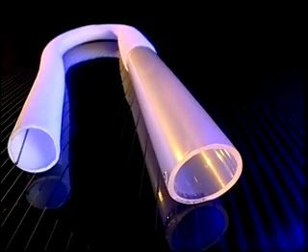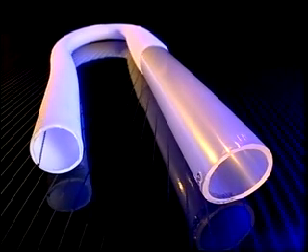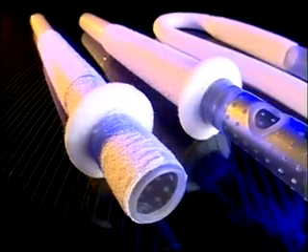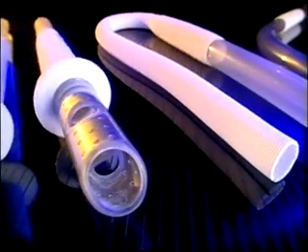The arterial grafts are woven polyester, available in 14mm or 18mm diameters, attached to rigid Thoralon tubes. Portions of these cannula are covered with polyester velour to encourage tissue ingrowth at the exit sites, which provides an effective barrier to infection.